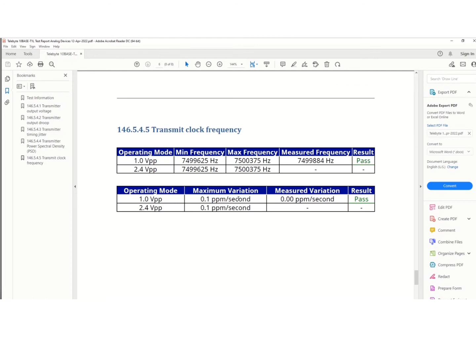And then we also looked at the short-term variation. That's within about 2 seconds, if there's any variation of the clock. The variation must be equal or less than 0.1 part per million per second, and we're measuring 0. So we passed the short-term variation test. And that's the automated report then, based on our manual testing.